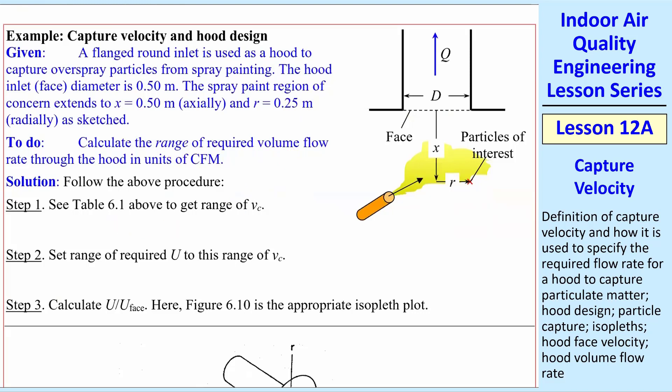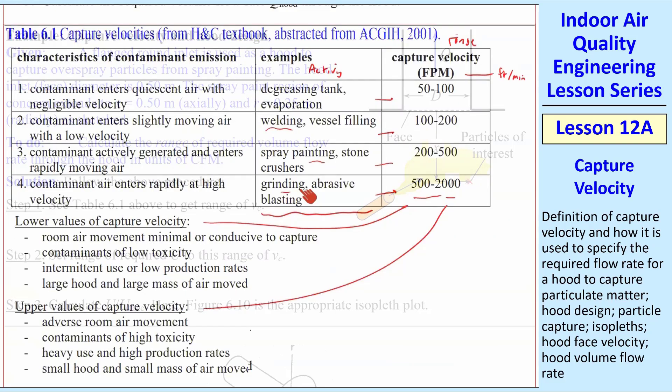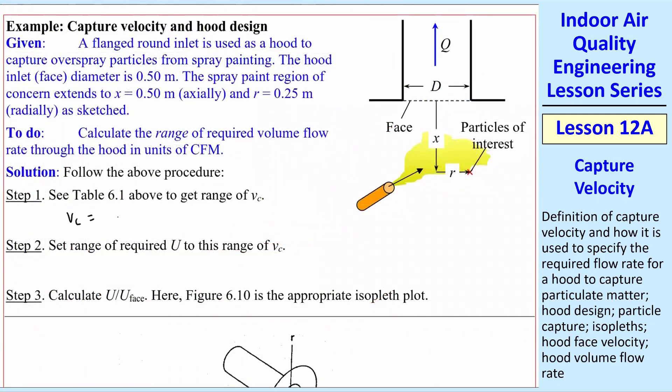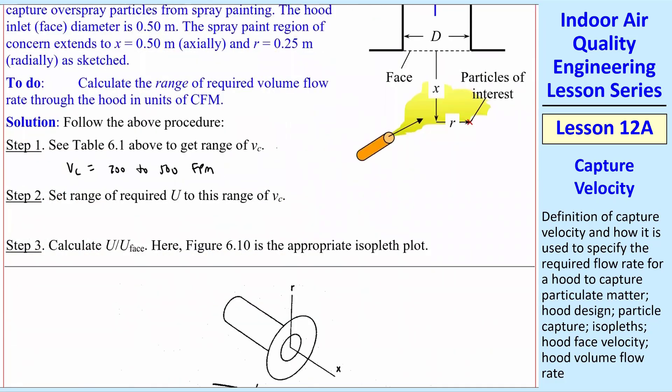And so the first thing I do is step one, and that is to look at Table 6.1 to get the range of VC. This is spray painting. So our VC is 200 to 500 feet per minute. So that's all there is to it. Step two is set the range of required U to this range of VC. Just set U equal VC.